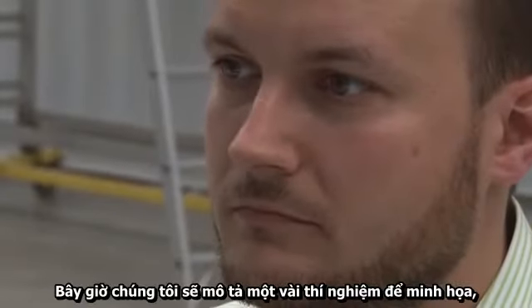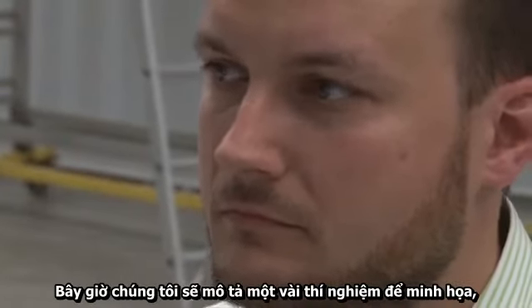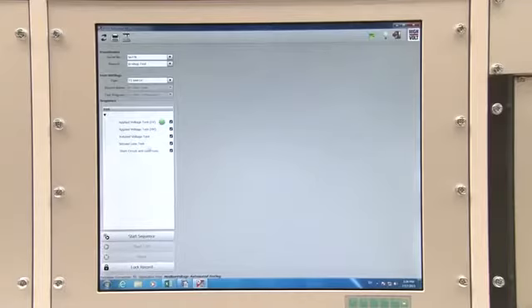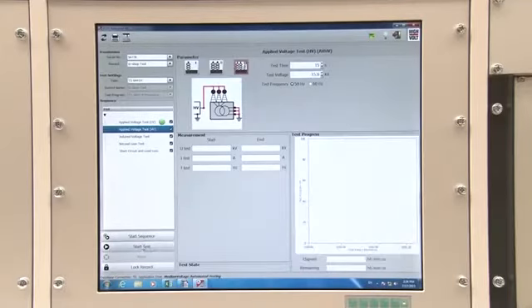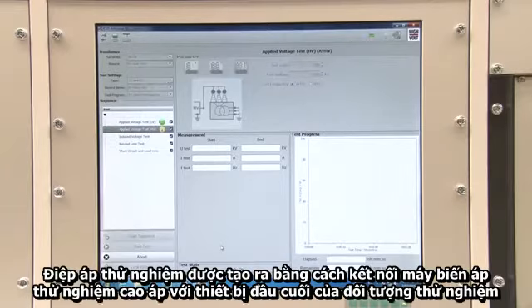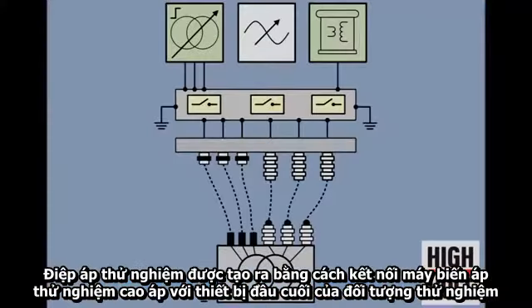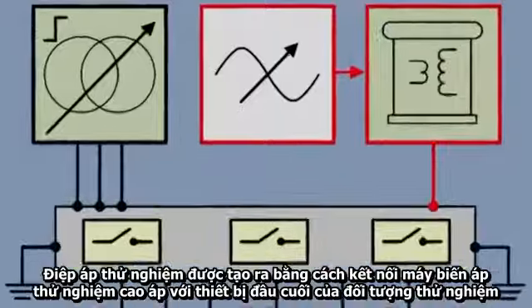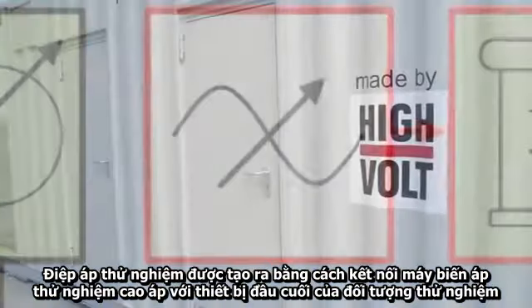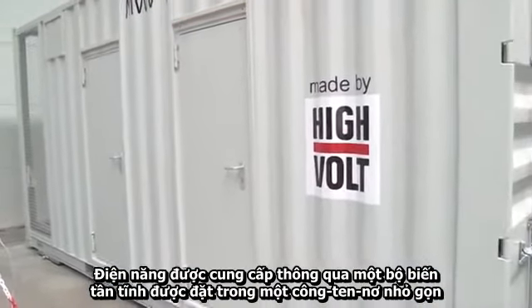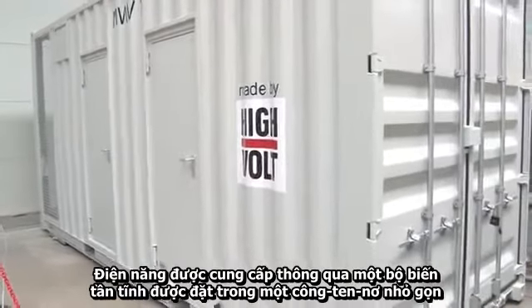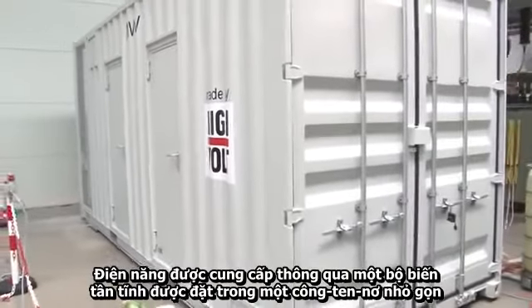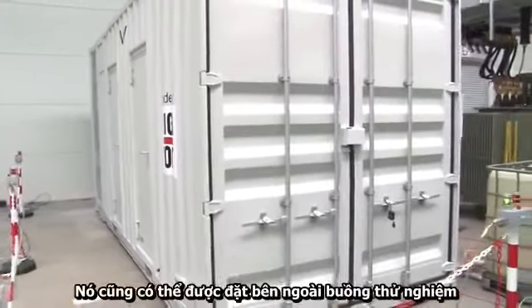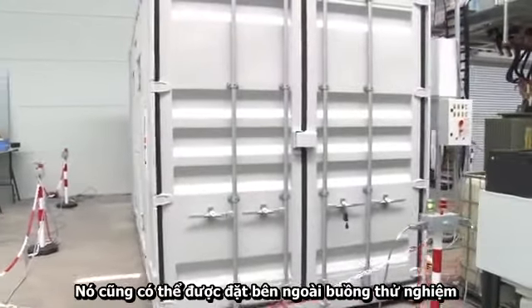Now we would like to describe a few tests as examples. Applied voltage test. The test voltage is generated by way of a high voltage test transformer connected to the terminals of the test object. The power is supplied via a static frequency converter, which is accommodated in a compact container. It can also be placed outside the test bay.